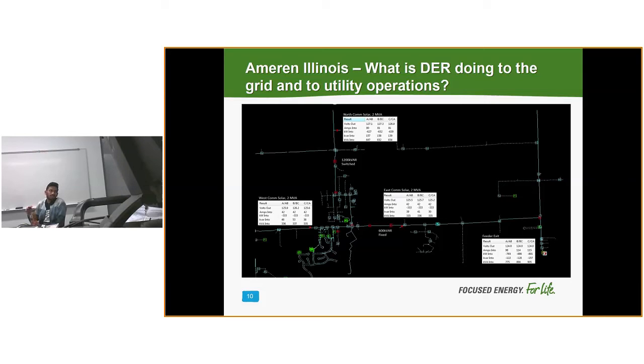There you go. So that would be one of the first things we'd do: come here and say, okay, we know voltage is correlated very strongly with VARs, right? I assume that cap bank is normally closed under normal conditions. It's closed there. Typically we run our cap banks on time and temperature parameters.